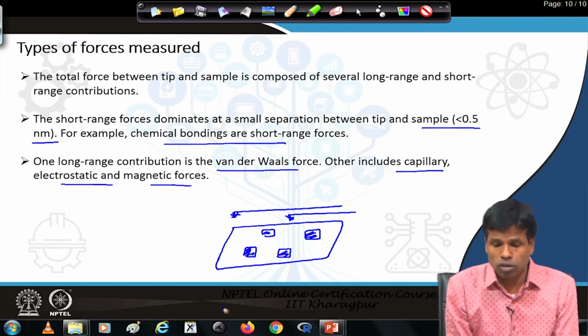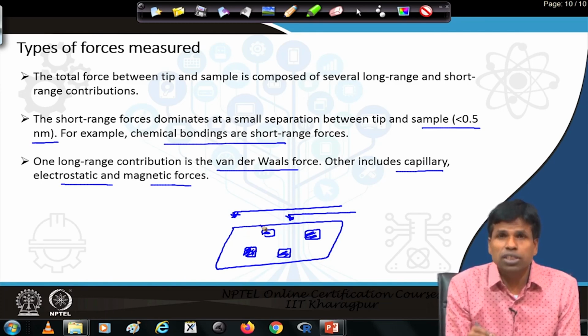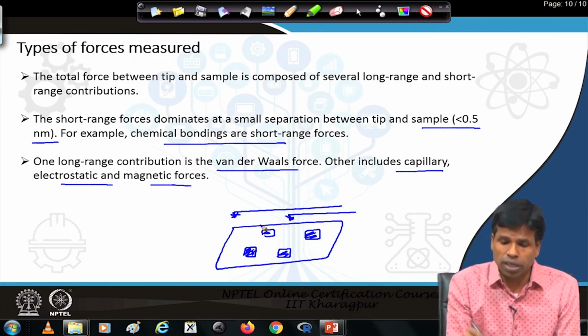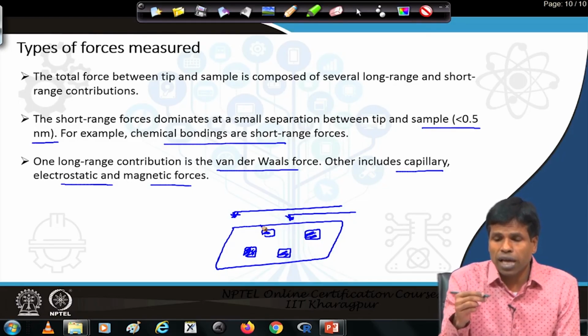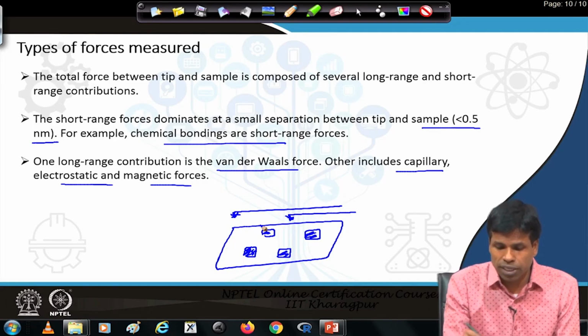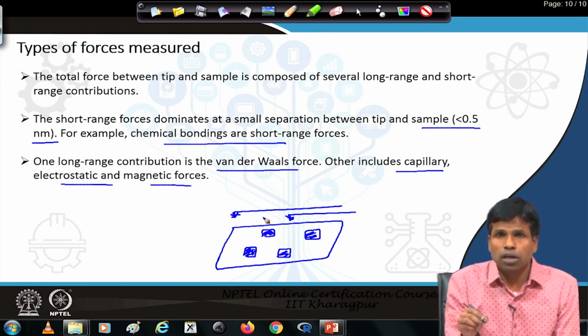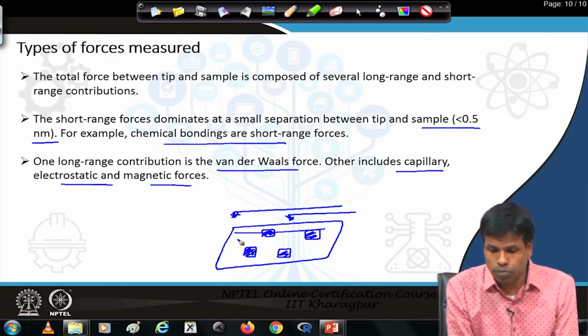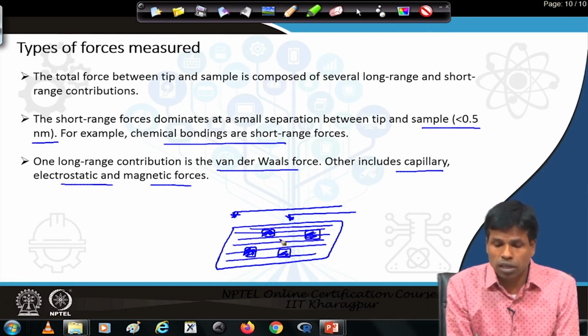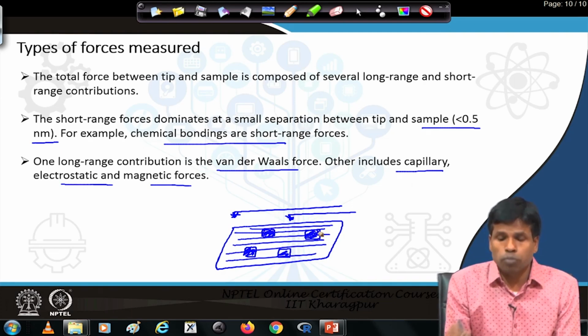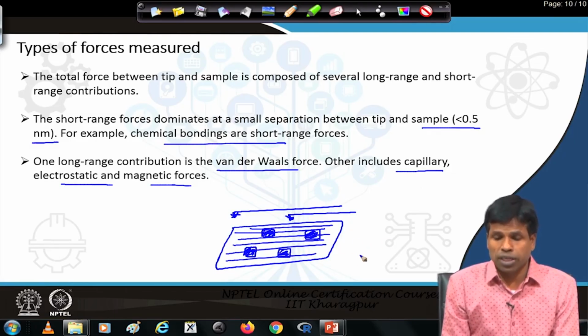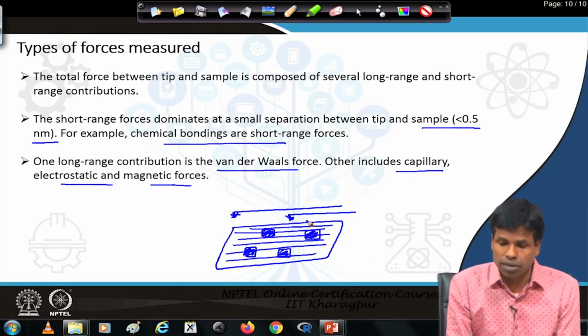And here the tip does not have to come very close to the sample, because magnetic force is a long range force. Even if the tip is more than 2-3 nanometer or 5 nanometer, 10 nanometer away from the sample surface, the tip can still experience the magnetic force. Wherever the tip sees a magnetic force, we know that a magnetic particle is present in that region. So the tip can scan from one side to the other, left to right, and produce a magnetic force map, thus creating a magnetic force microscopic image, telling us how the magnetic particles are distributed on the sample.